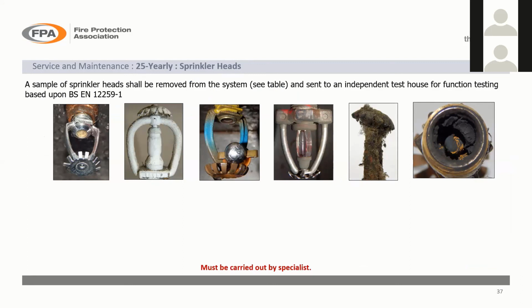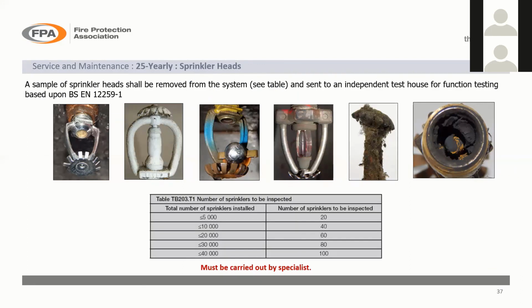The sort of sampling that you're looking at would be defined in the table in Annex K and TB203. Generally speaking, most of the batches that we receive tend to be within that sort of 20 sprinklers. So normally you send 20 in to the FPA for testing, and a report is produced. And obviously, if they fail, then you might have to replace the sprinklers in your premises. But in a lot of cases, they do pass. But that is a requirement. That's the maintenance requirement that you need to get done after 25 years.